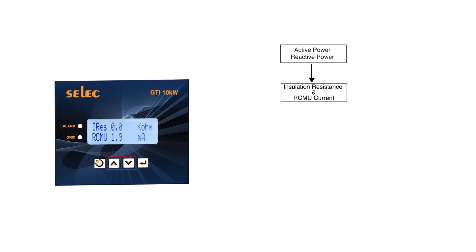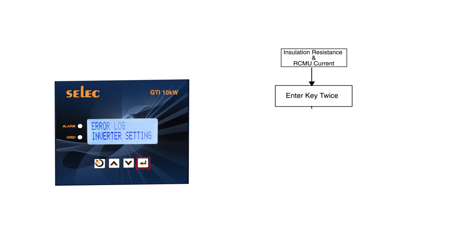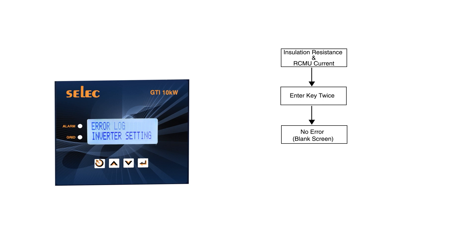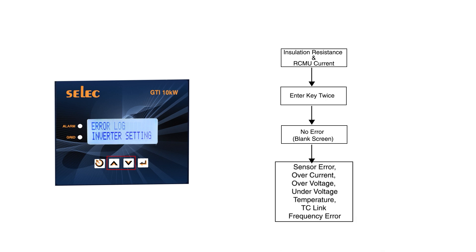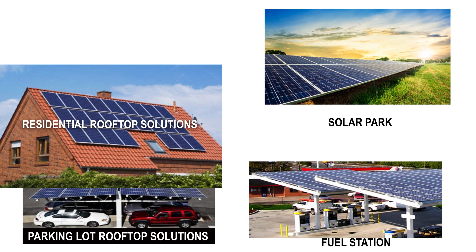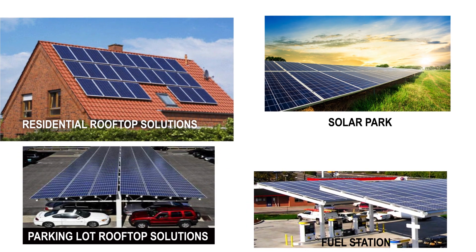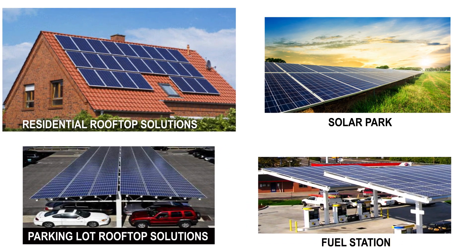Pressing the Down key shows insulation resistance and RCMU current. Use the Up and Down keys to navigate. To check errors, press the Enter key twice — if there are no errors, the screen will be blank. Use the Up and Down buttons to scroll through errors such as ADC sensor error, over current, over voltage, under voltage, temperature, DC link, and frequency error. The inverter can store up to the last 20 errors. Applications include residential rooftop solutions, solar park, parking lot rooftop solutions, and fuel stations.